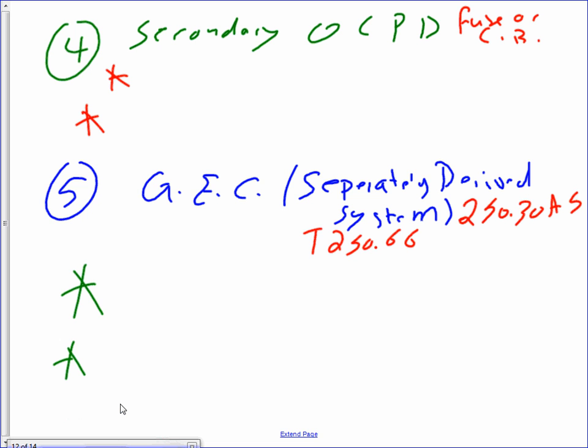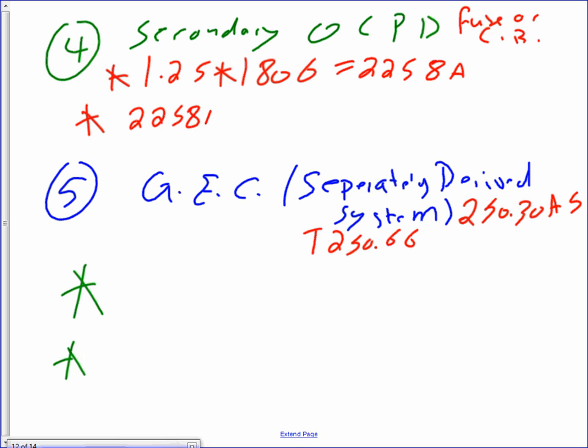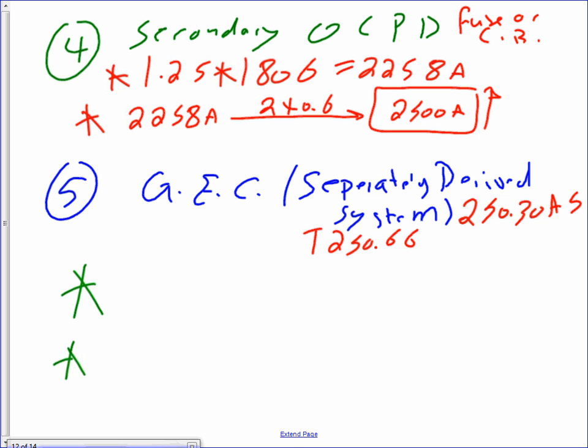Good. Okay, let's go to the fuse or the circuit breaker, guys. That's number 4. For the fuse or the circuit breaker, 1.25, same thing. Multiply that baby, from the NEC code book, by 1806. That'll get you, gentlemen, 2258 amps. You take the 2258 amps to 240.6, and you go to 2500 amp. Your next non-adjustable circuit breaker will be 2500 amp. Now, what they typically do, guys, is go to that circuit breaker and tweak it down to match your conductors. Did you guys hear me? We size our conductors to 2258, right? And you adjust that circuit breaker to match your conductors.